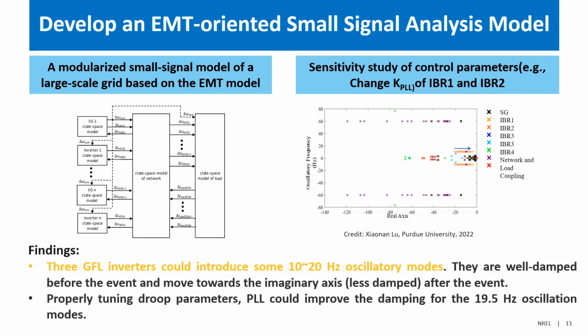We definitely saw those oscillatory modes becoming less damped. Then we tuned the control parameters and found that tuning the droop parameters as well as the PLLs could be the most efficient way to damp these oscillations.